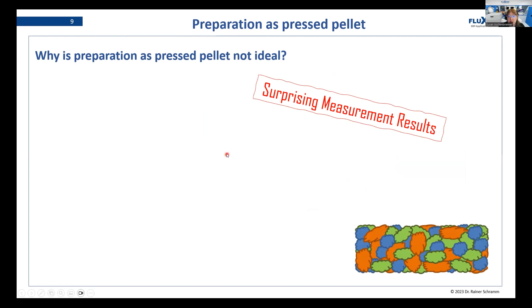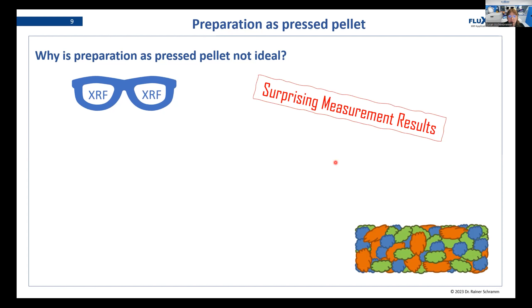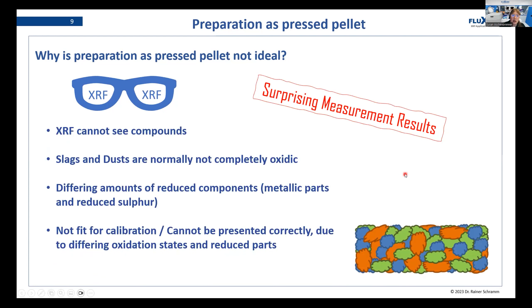To understand why this is happening, you have to see that we are looking at samples using XRF as a measurement method, and XRF cannot see compounds. Slags and dusts are normally not completely oxidic, which means that we can have differing amounts of reduced components — metallic parts or reduced sulfur — and this plays tricks on us because XRF cannot see it.